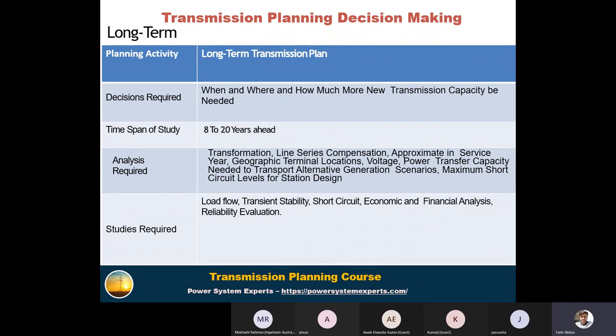So the analysis required, same analysis, parameters: the power transfer capacity, the thermal limits, the line series compensation, because in long-term planning we see the parameters from a larger perspective rather than going into details. And similarly, the study required is only the load flow analysis. Basically, it tells us where the power flows within the network. And next, transient stability, whether the network is stable with this new network or not. And short circuit basically tells us whether, with the future addition of generation, the level of your short circuit is within limit or not, and the level of your breakers are within limit or not.